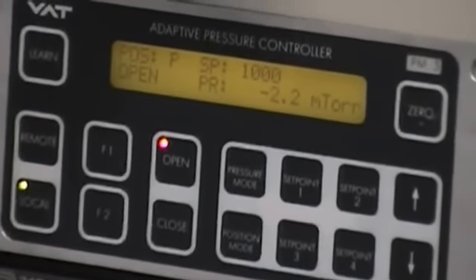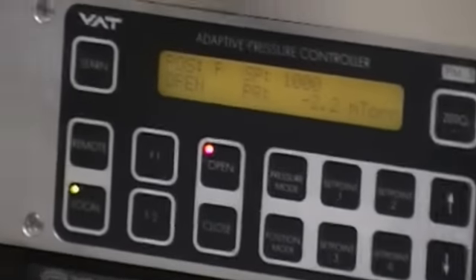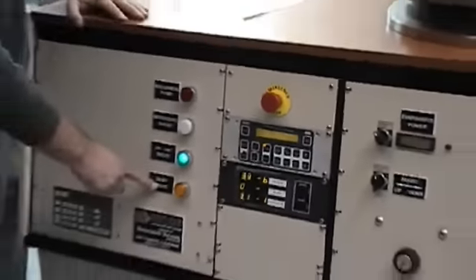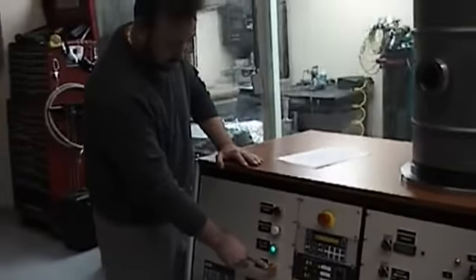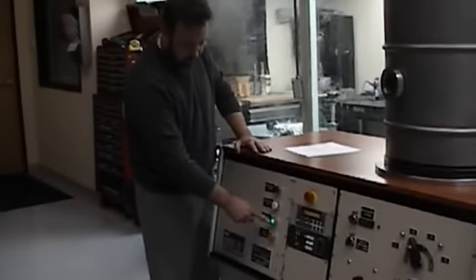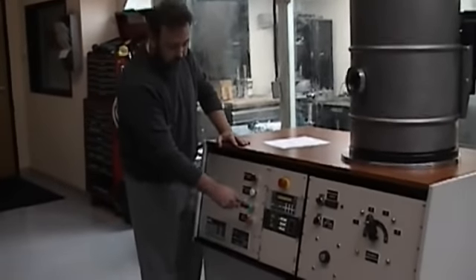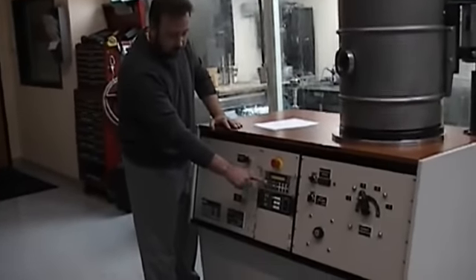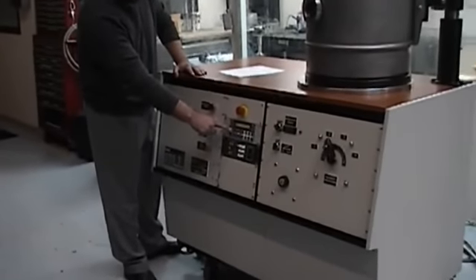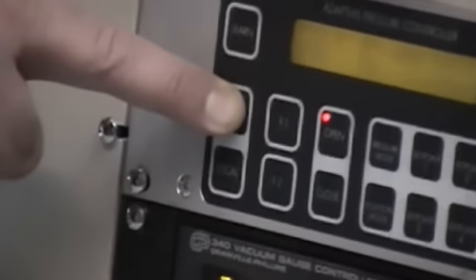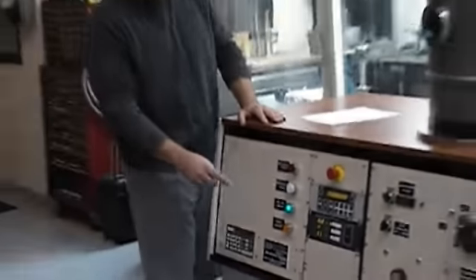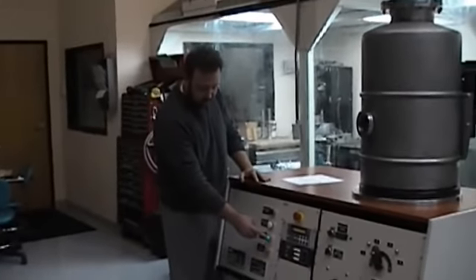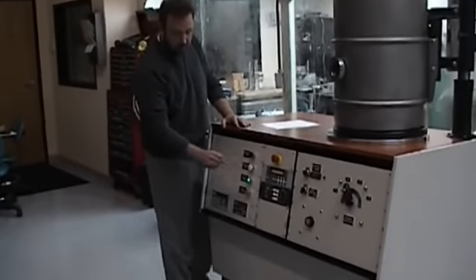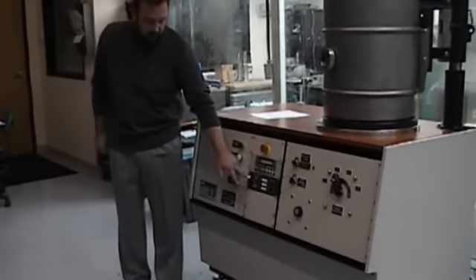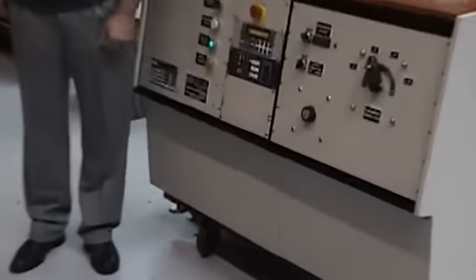If you do it this way, you are bypassing this switch and the safety interlock, which does not allow you to turn on the vent valve unless this valve is closed. That's why we set that up that way. So to put it back in remote, operate the way we have designed it, you would hold it until the button is illuminated. Leave it in remote. It should stay there. To operate the gate valve, before I shut down the gate valve, we're at 3 times 10 to the minus 6.